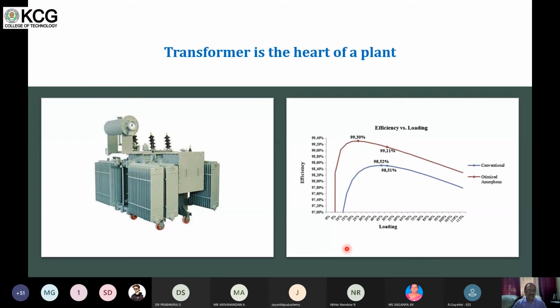In CPCL, Chennai Petroleum Corporation Limited, which is owned by the IOC, we did an audit on all unmanned substations. Approximately 74 transformers are there, distribution transformers, mostly of 1600 or 2000 kVA. During our audit, we found out that around 15 transformers can be switched off completely because they were being loaded very, very poorly, around this zone, 5 to 10%. So we suggested, in order to improve the power factor, load factor, switch off a few transformers.